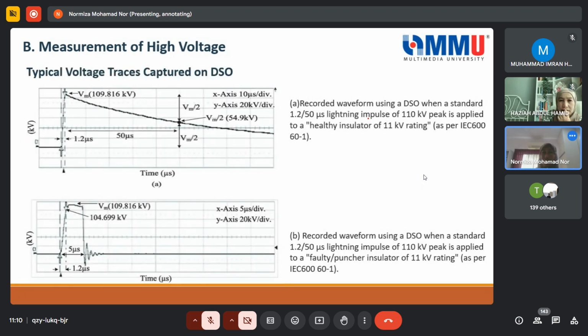So this is the typical voltage captured on the DSO. This one I got from the internet, not my own reading. But anyway, you can see here the recording for a 1.2/50 impulse to a healthy insulator of 11 kV. So this is what they observe from the oscilloscope. The y-axis is 20 kV per division, whereas the x-axis is 10 microseconds per division.